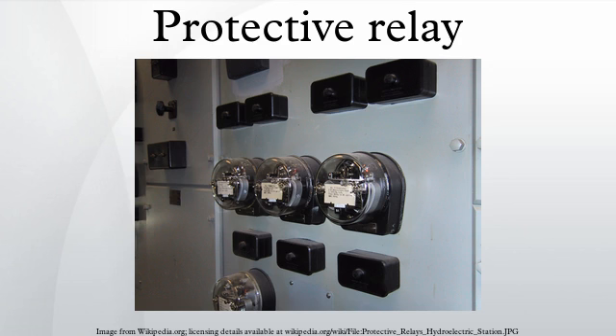Microprocessor-based digital protection relays now emulate the original devices, as well as providing types of protection and supervision impractical with electromechanical relays. In many cases a single microprocessor relay provides functions that would take two or more electromechanical devices. By combining several functions in one case, numerical relays also save capital cost and maintenance cost over electromechanical relays. However, due to their very long lifespan, tens of thousands of these silent sentinels are still protecting transmission lines and electrical apparatus all over the world.